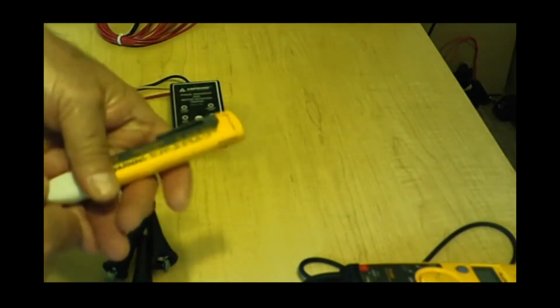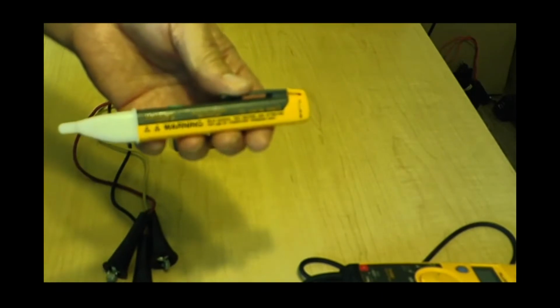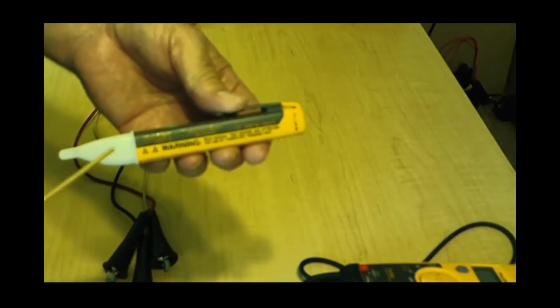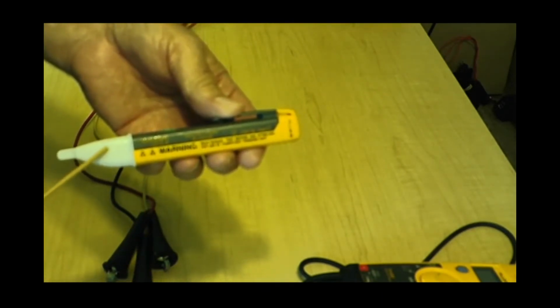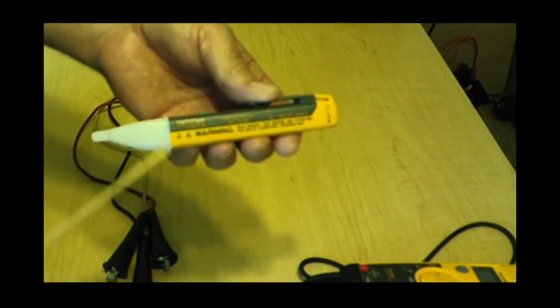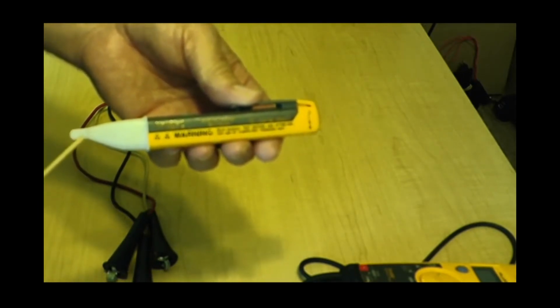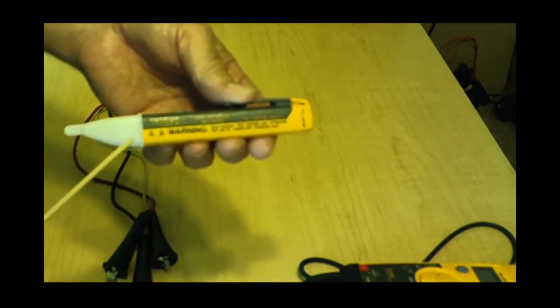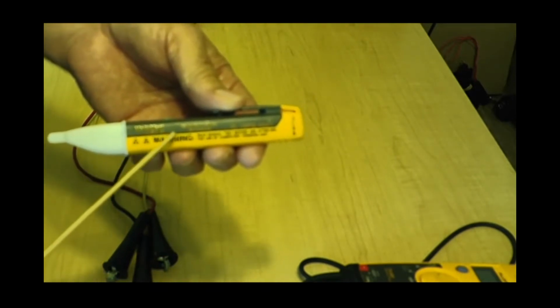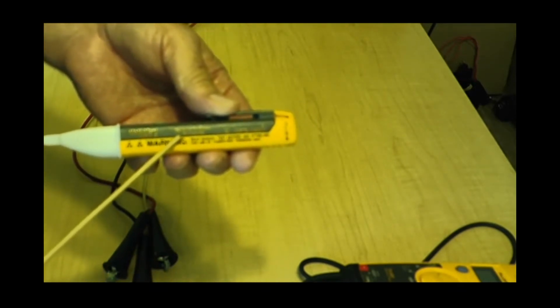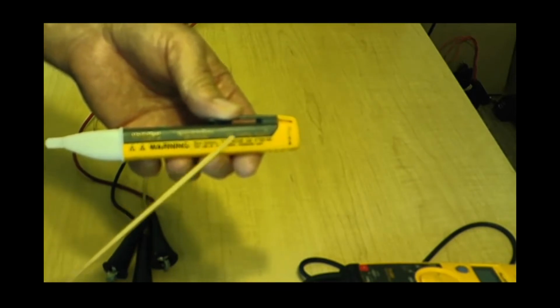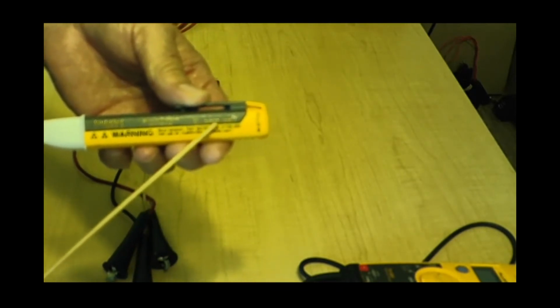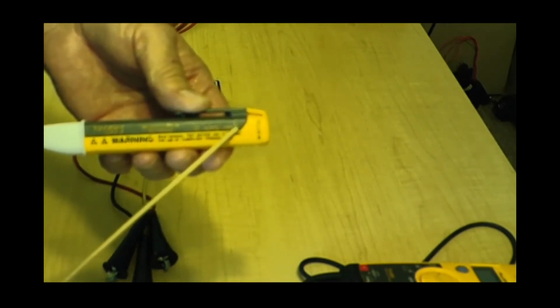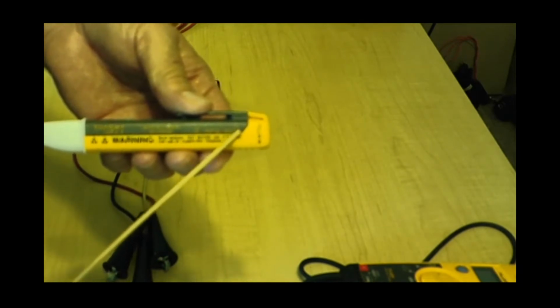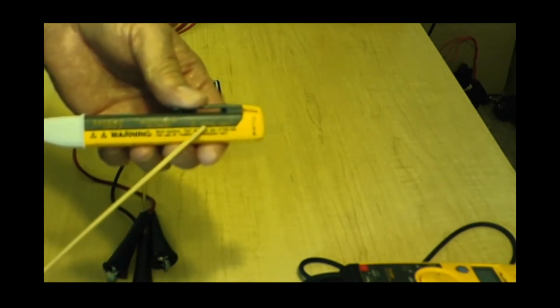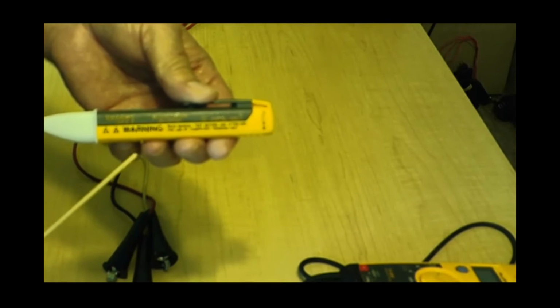Let's go with this meter. This is very popular for many people. This is what's called a tester or an indicator. These things have the nickname Widowmaker, and there's a reason for this. Now, this has got a rating right here. This one is rated from 90 to 1000 volts AC. It's category 4 up to 1000 volts. So as long as it's 1000 volts and less, I could use it in category 4 locations.